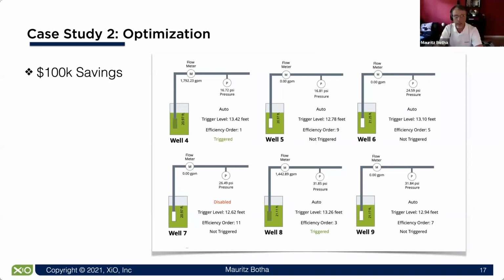So if you look at the details in this screenshot, the first one is a trigger level, and if you look at all the different pumps, the trigger levels are different. That means as the reservoir drops down, the pump with the highest level comes in first, followed by the second one if it can't keep up, followed by the third, up to the 11th. You'll also see something that says efficiency order — that's just the order in which the pumps will start running.